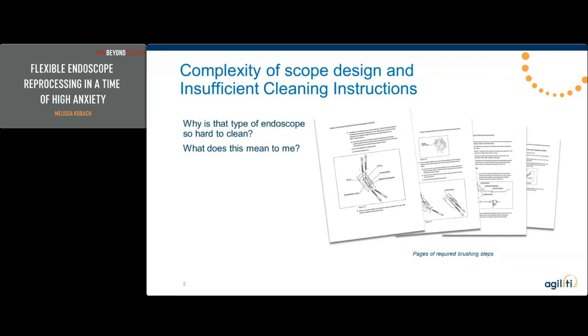The ERCP moment in time was different in a very important way. The IFU instructions, brushes, and cleaning procedure were not sufficient, and this was not limited to just one manufacturer. What do you do when your IFU is wrong? This is what you're supposed to go by. On top of this, there was also a design flaw within one of the leading models that accounted for the majority of these infections. Add in the complexity with cleaning the elevator, a few patients with resistant strains of CRE, and pow, you have a perfect storm.